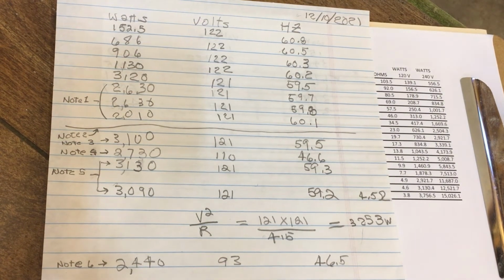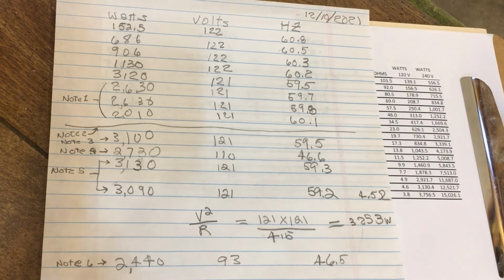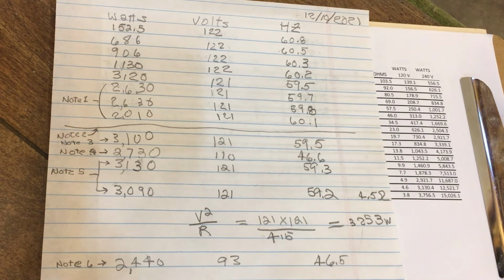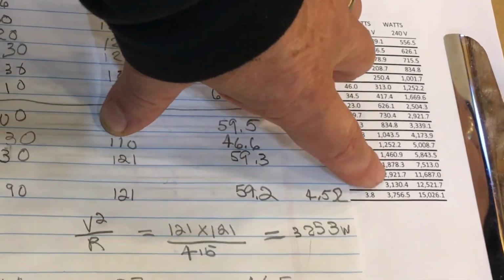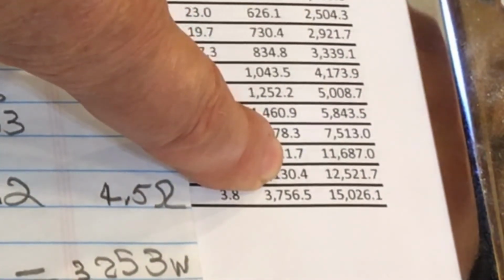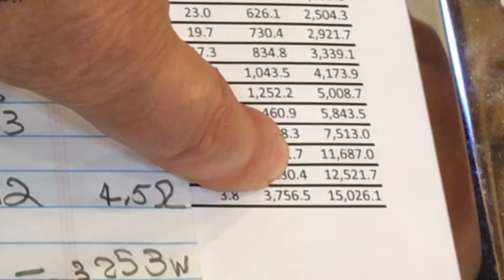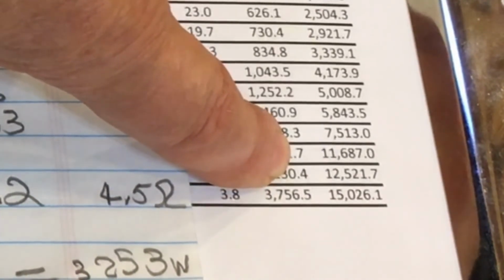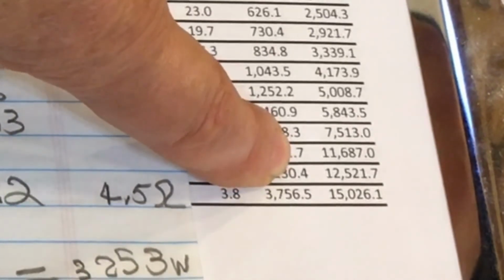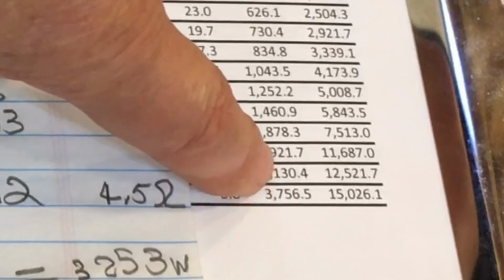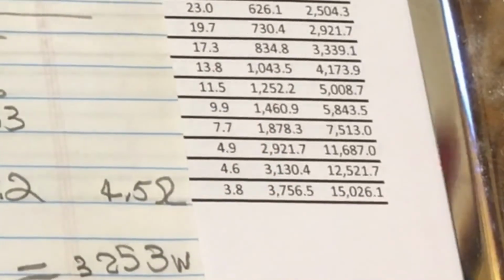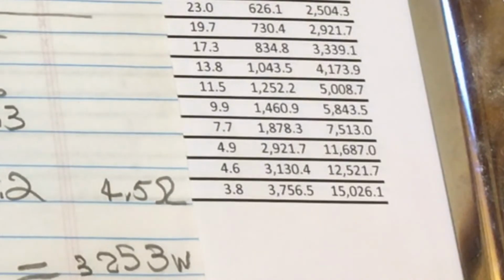At this point, I decided to go for broke. I went ahead and put the minimum amount of resistance, which equates to the maximum amount of electrical load that this load bank could put on a 120 volt system. And I would expect, according to my little table, if everything were ideal, maybe I would have seen as much as 3,700 watts, give or take. This number I'm pointing to here is just a theoretical number, but it depends on exactly what the voltage is and the temperature of the heating elements and everything else.